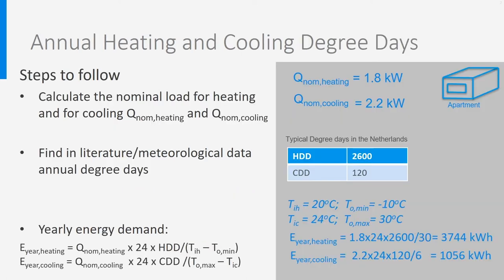How does a calculation with degree days look like? On the left the steps, on the right the example. Here again, we need first to have determined the nominal powers for heating and cooling — in our example, 1.8 and 2.2 kilowatt. Then you need to find what the degree days are in your region. In the Netherlands, the heating degree days are around 2600, while the cooling degree days are very low for residential buildings, around 120. Finally, you need to use these equations. You see in these equations T_iH and T_iC, which are the indoor temperatures used when calculating the nominal powers for heating and cooling — respectively 20 and 24 degrees C in our example.